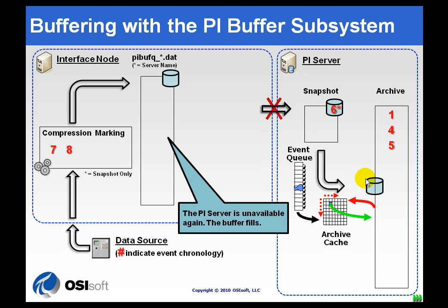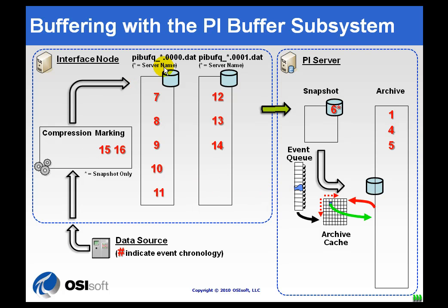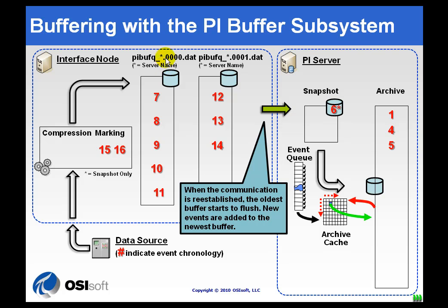If the same situation occurs again but doesn't resolve quickly, and the first buffer fills, then we are going to overflow to a second buffer. This buffer is called pibufq underscore and then the name of your server, with numbers appended at the end indicating which file it is. If the first one fills, we start a second one. Once communication is reestablished, since this is a FIFO queue, we start retrieving data beginning with the first data that came in — values 7, 8, 9, 10, etc.